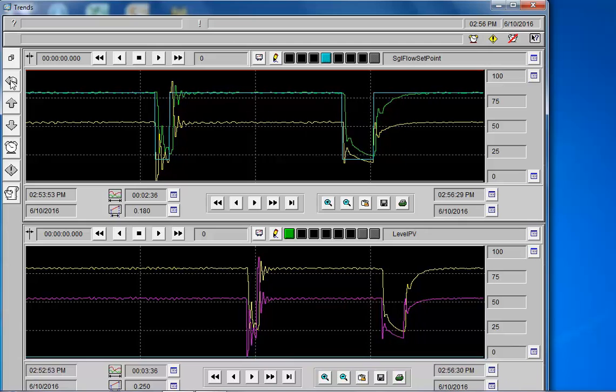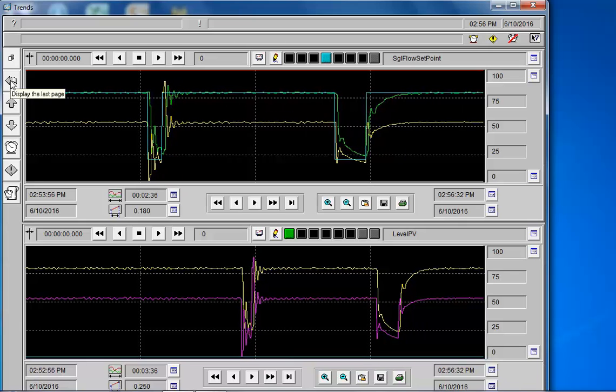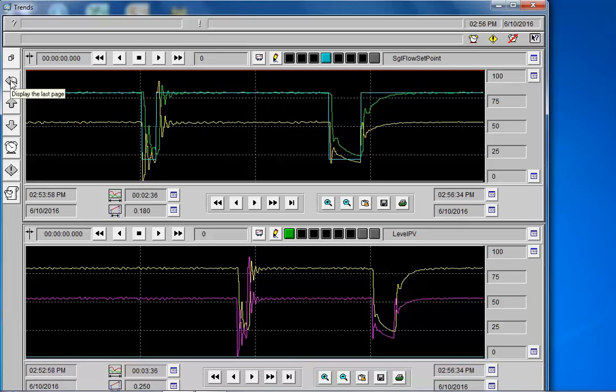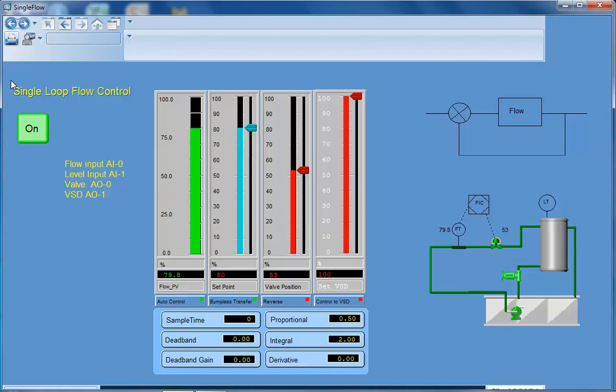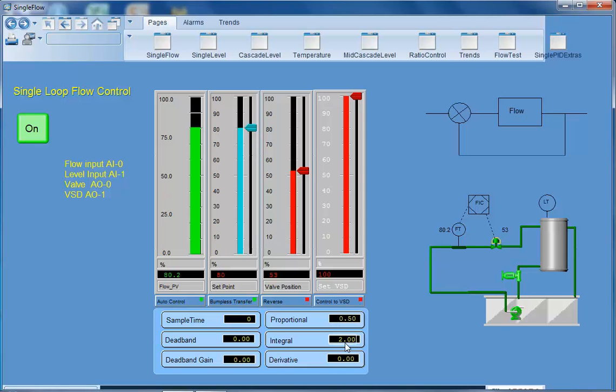So we can decrease our P further, but we might in fact be better off looking at going back to our I, our integral time. So to decrease that moves us towards instability. Let us try halving. And once again, through our 20 to 80% range. Letting it stabilize.